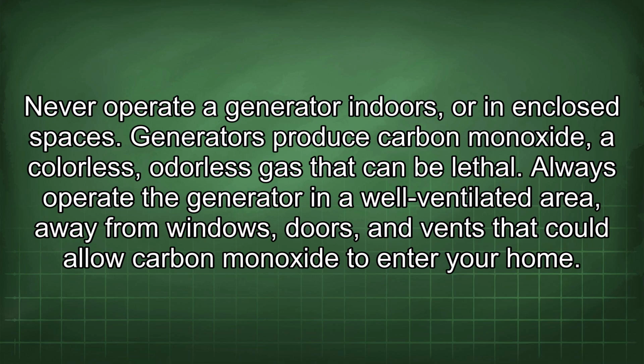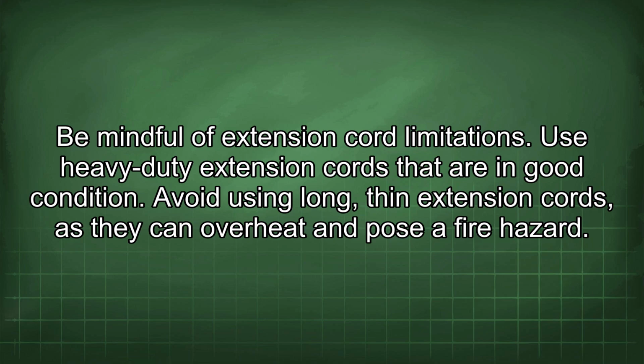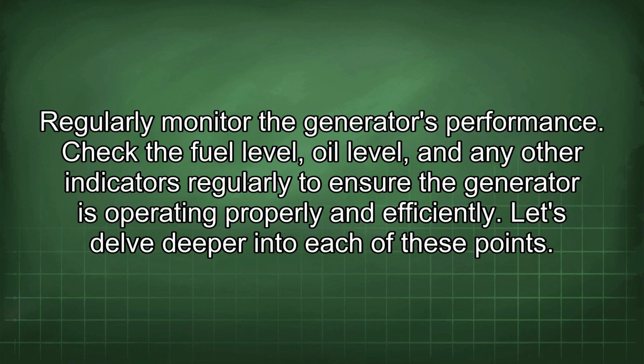Never operate a generator indoors or in enclosed spaces. Generators produce carbon monoxide, a colorless, odorless gas that can be lethal. Always operate the generator in a well-ventilated area, away from windows, doors, and vents that could allow carbon monoxide to enter your home. Be mindful of extension cord limitations. Use heavy-duty extension cords that are in good condition. Avoid using long, thin extension cords, as they can overheat and pose a fire hazard. Regularly monitor the generator's performance. Check the fuel level, oil level, and any other indicators regularly to ensure the generator is operating properly and efficiently.